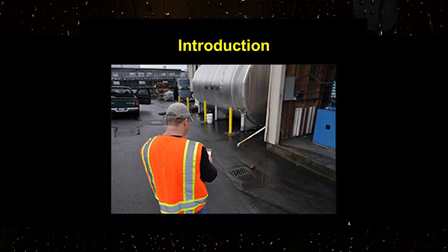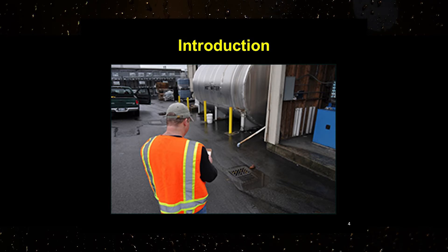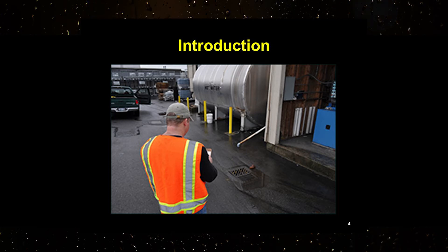Stormwater permits require the visual assessment be conducted as part of the comprehensive inspection. Comprehensive inspections are required quarterly or on an alternate schedule approved by the Water Resource Division of EGLE. The comprehensive inspection must be conducted by an industrial stormwater certified operator, and the visual assessment must be completed within 30 days before or after this inspection.